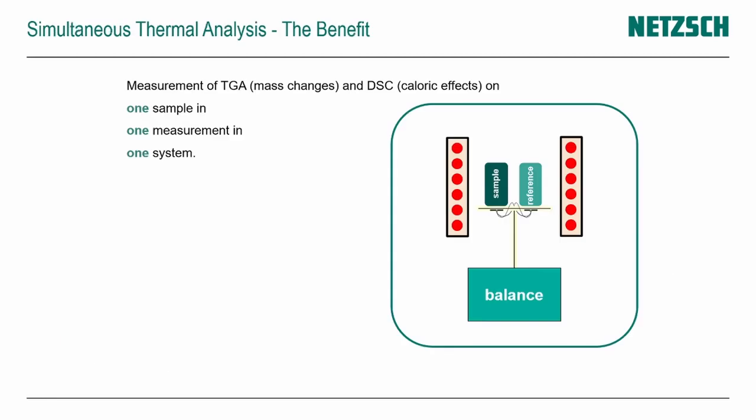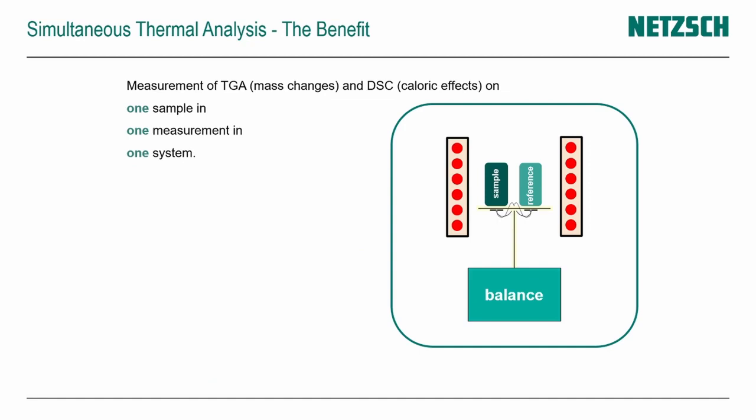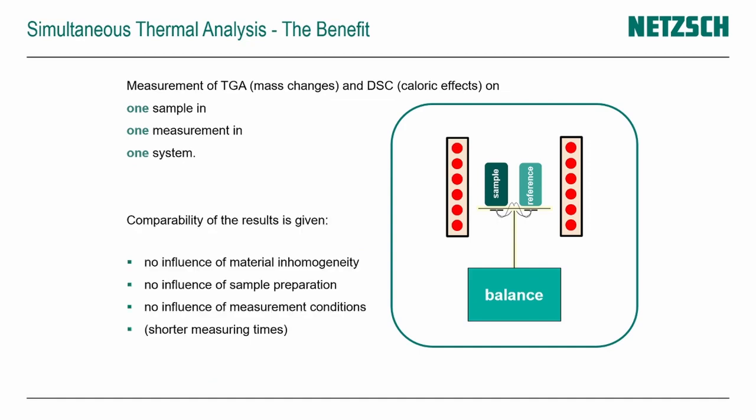The main benefit of the STA technique is that we do all the measurements — TGA and DSC — on one sample, in one measurement, on one system. Therefore, we have no problems with material inhomogeneity, sample preparation, or the influence of measurement conditions, because it is one sample in one measurement. It sounds quite good.